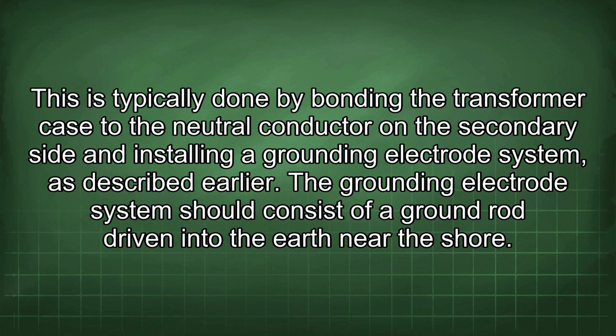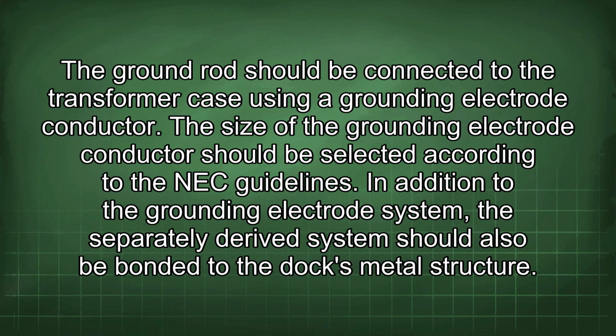This is typically done by bonding the transformer case to the neutral conductor on the secondary side and installing a grounding electrode system, as described earlier. The grounding electrode system should consist of a ground rod driven into the earth near the shore. The ground rod should be connected to the transformer case using a grounding electrode conductor. The size of the grounding electrode conductor should be selected according to the NEC guidelines.